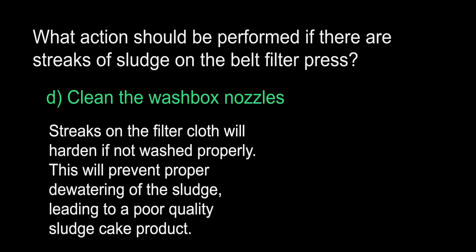The answer is D, clean the wash box nozzles. Every belt filter press is equipped with nozzles that continually spray water onto the filter cloth. On a belt filter press, these nozzles are located after sludge cake has been removed but before more sludge is applied. This keeps residual sludge and polymer from sticking to the filter cloth. If improper washing of the filter cloth occurs, streaks will appear and then dry, which will make the cloth less porous, allowing less water to be removed from the sludge. This leads to a sludge cake product with a lower percentage of solids.